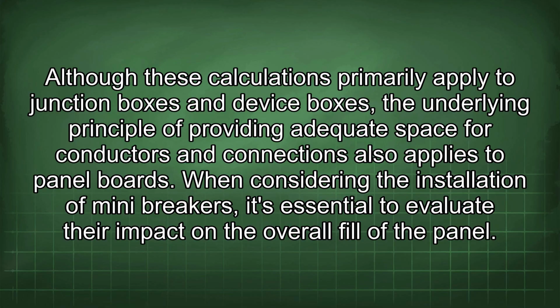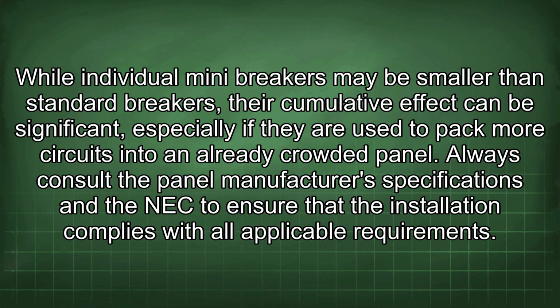When considering the installation of mini breakers, it's essential to evaluate their impact on the overall fill of the panel. While individual mini breakers may be smaller than standard breakers, their cumulative effect can be significant, especially if they are used to pack more circuits into an already crowded panel. Always consult the panel manufacturer's specifications and the NEC to ensure that the installation complies with all applicable requirements.